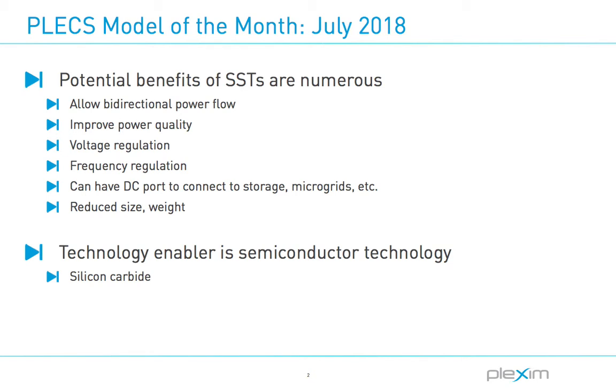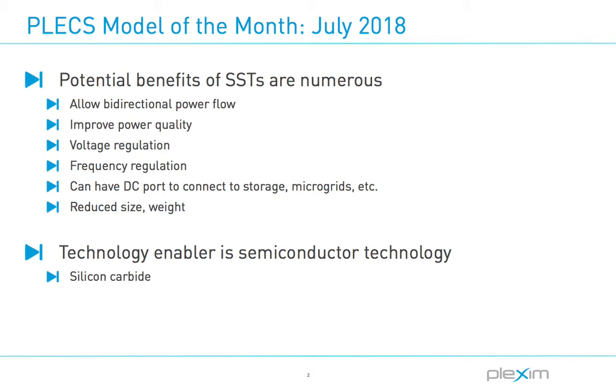An SST uses multiple stages of power converters with a medium to high frequency isolation stage. Depending on the SST design, added benefits can include allowing bidirectional flow of power, improving power quality, voltage and frequency regulation, and the ability to interface to AC or DC systems. Until recent advancements in semiconductor technology, SSTs were limited to academic research and not practical for true grid distribution power levels. However, silicon carbide devices, in particular, have led to increased interest and funding in this area.